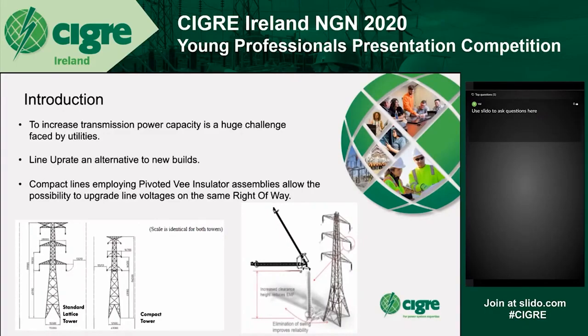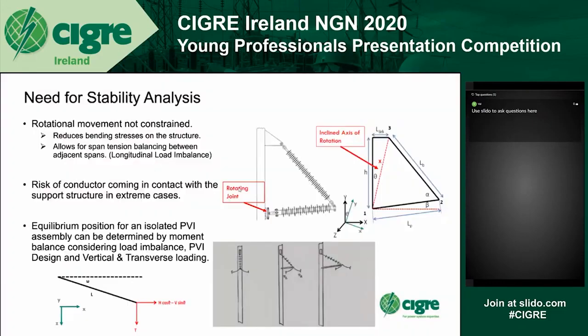A PVI assembly eliminates the swing of the insulator towards the support structure, reducing the required clearances and thereby reducing the overall footprint of the line, as can be seen in the comparison between the standard lattice tower and a compact tower employing a PVI design. A conductor in a PVI design is allowed to move longitudinally along the span, as the PVI assembly itself can rotate on an inclined axis of rotation shown on the right.